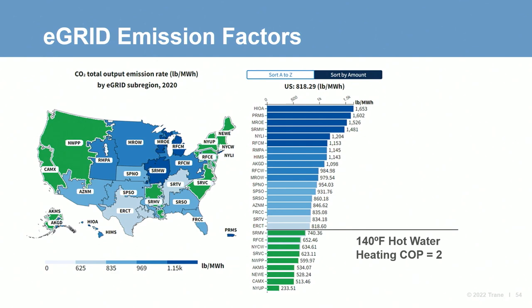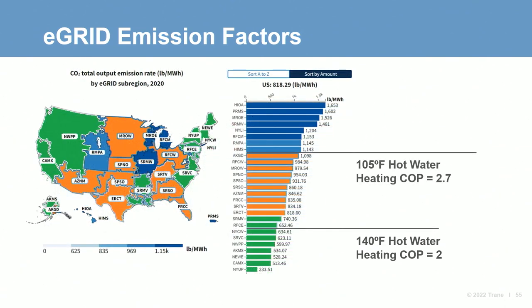Alternatively, if we took the same design but lowered the hot water set point to 105 degrees, our break-even carbon emission factor would be around 1,100 pounds of CO2e per megawatt hour. You can see that the increased efficiency would further reduce carbon emissions and add more utility grids to the map. Designing for lower hot water set points can provide increased energy efficiency, lower emissions, and provide the design team with more heat pump equipment options.